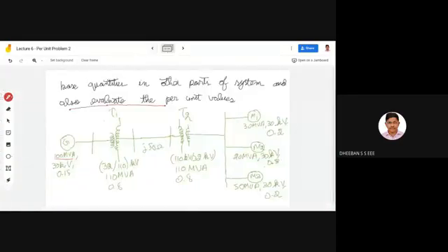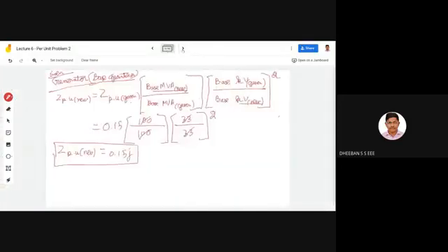As I said already, up to here you have to consider the base voltage, base kV new, to be 33 kV, and after that you have to revise it. You're making a jump. When you make a jump, you have to revise your voltage, and after that, that value only till transformer 2 you have to use as the revised base kV new. So don't get confused.